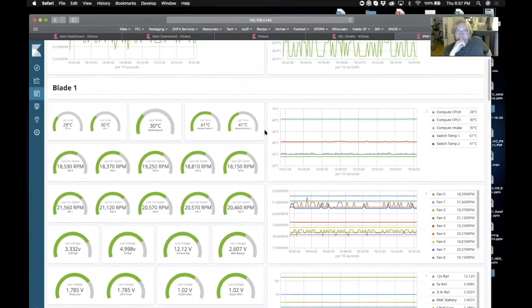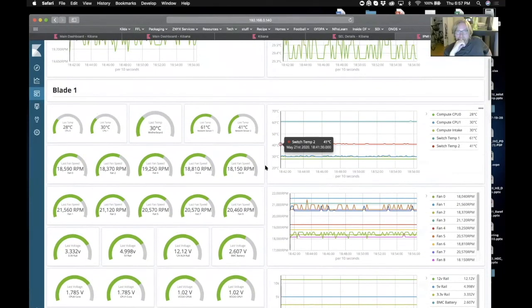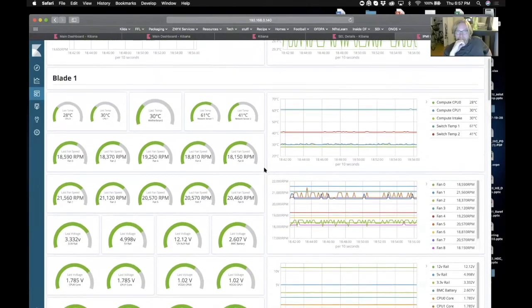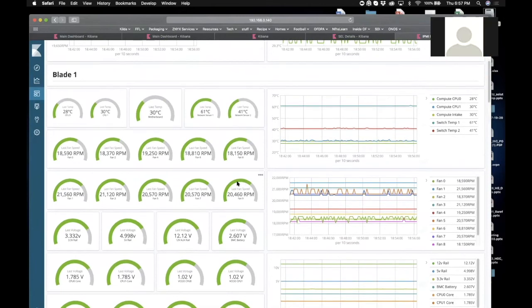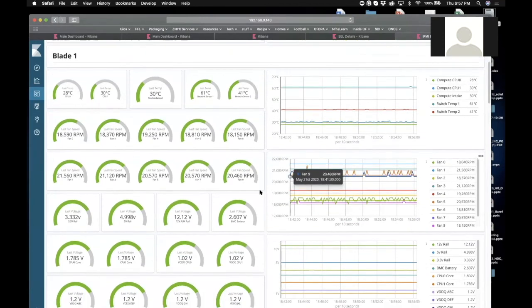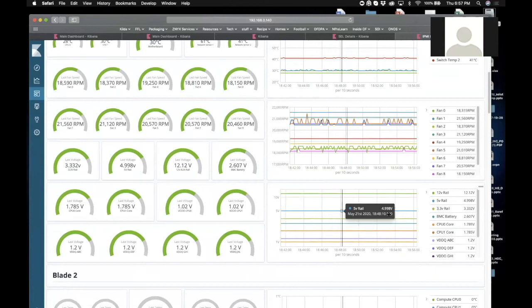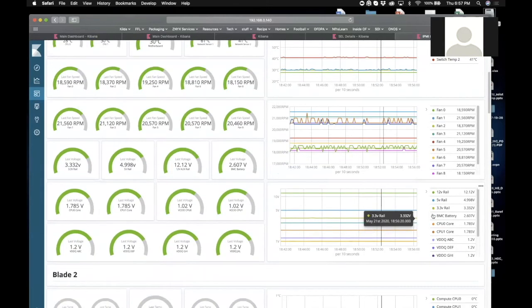They give indications like if a bearing in a fan is starting to seize up it's going to start slowing down before it stops, so you'll be able to see that through the time series database. And then you get an idea of all the voltage rails coming in. And this is for blade one, so you can get a snapshot of what the current values are and then you can scroll through time to see how steady that is.